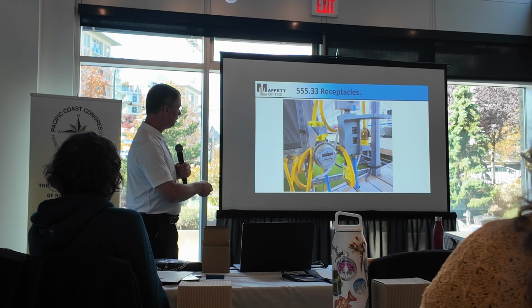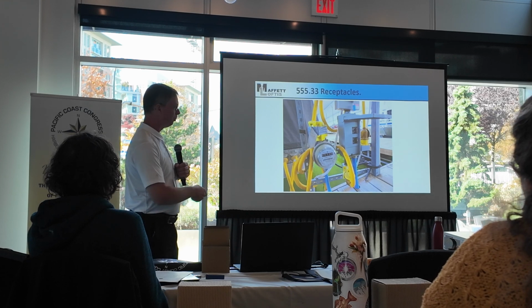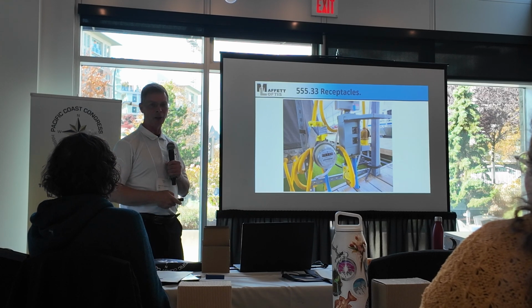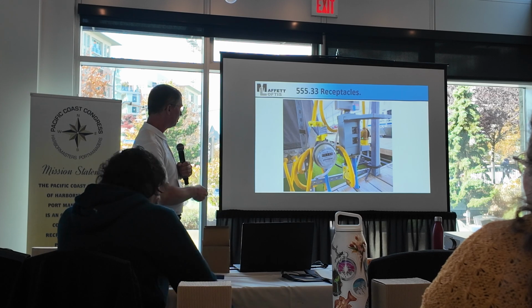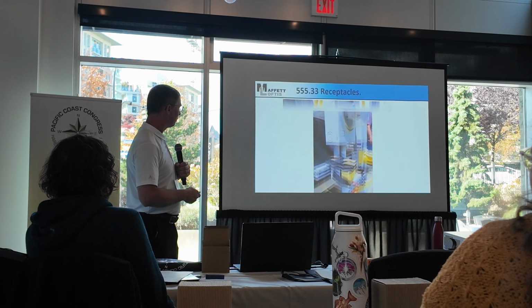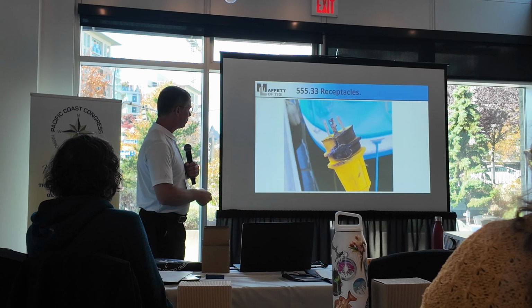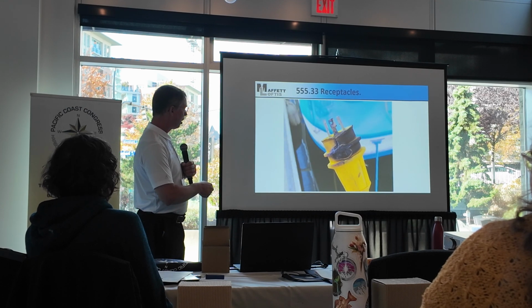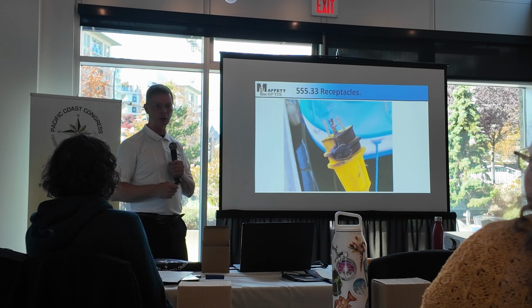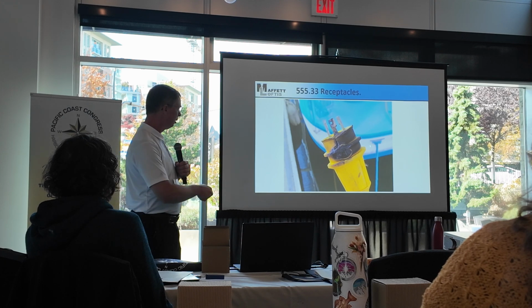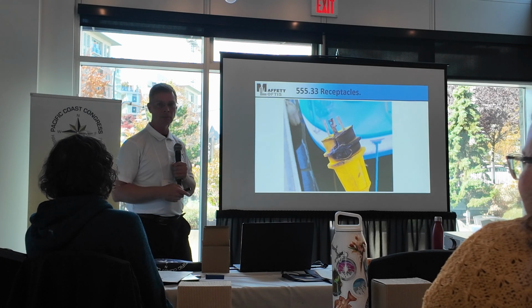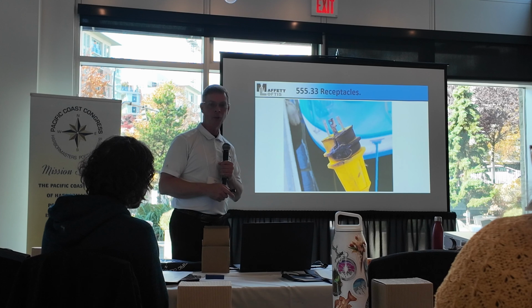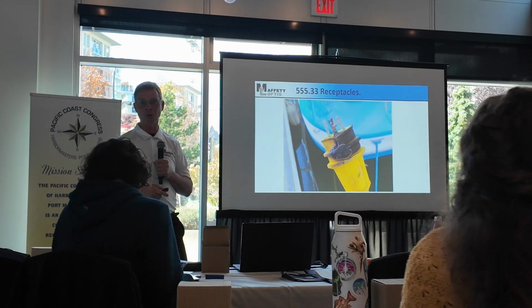Does having plugs straight up meet UL wet listed ratings? No. Straight into it, straight down. I don't know why that's happening. All kinds of issues going on. And that's what happens. That was the top pin right there, had a high resistance connection, heated up, and luckily we didn't have a fire. Well, it melted anyway, yeah. Smoke was coming out, I'm sure.